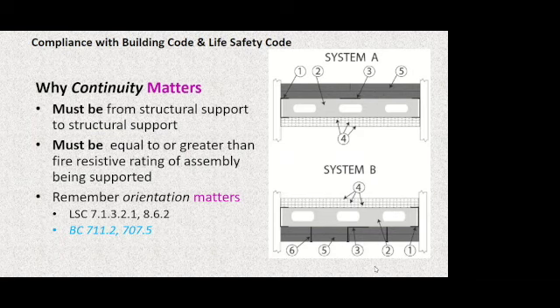It demands a 2-hour wall on each side of that horizontal assembly, and that 2-hour wall must rest on the floor and go up to the slab above, and it creates an H, if you will. It provides the continuity support that's required by 707.5. Remember, orientation matters. That continuity support concept says I must have the entire assembly supported, structurally supported by fire resistance elements equal or greater than the assembly's demands. So if I have a duct system that needs to be 2-hour fire rated according to the code path, I need to have continuity construction 2 or more hours connected to a wall, connected to a floor, connected to a beam, a girder, everything that it connects to structurally back to the foundation of the building must be equal or greater than 2 hours.